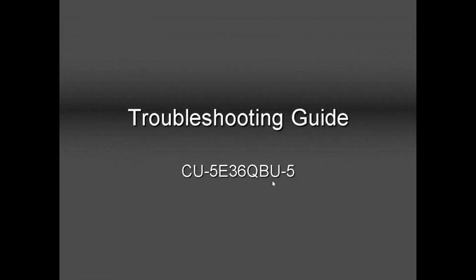Then we have the priority mode. The priority mode is given to the indoor unit of the highest capacity. So what that means, the highest capacity is given the priority, even when other units were running. Even when other units were running in heating and you want cooling, and if that unit is the biggest or highest capacity, you can flip the mode easily. But you cannot flip other modes easily if the priority mode was in operation.